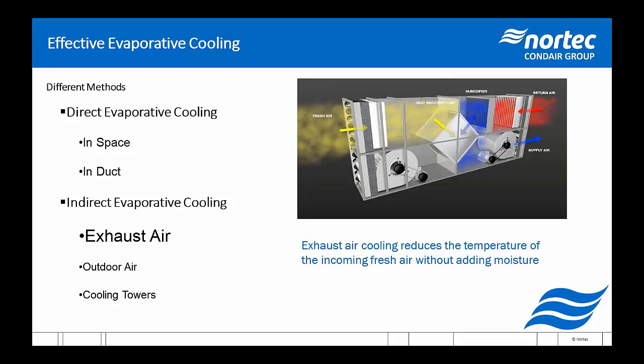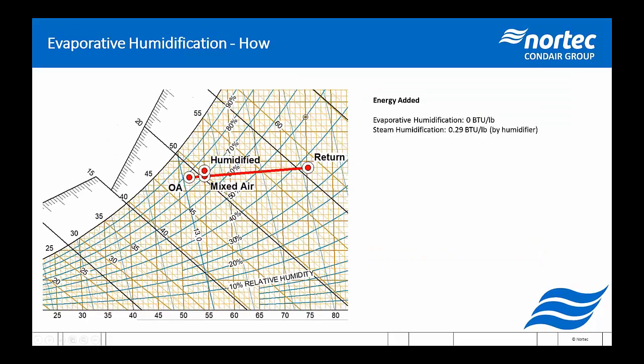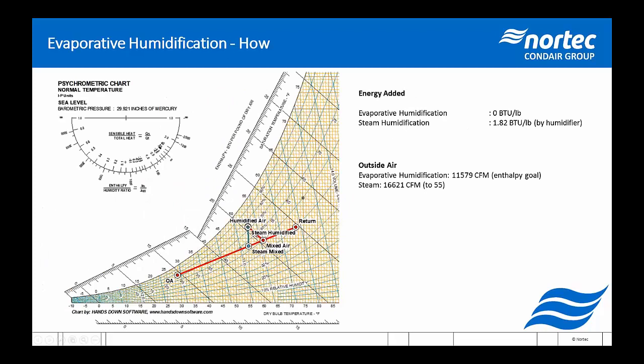Depends on the amount of outside air we need, of course, but typically we'd control it with an enthalpy goal. So if I go back to, well, it's not the best slide. This is the best slide for this. If I go back to this, what we'll be aiming for is we'll put typically enthalpy sensors in the economizer system. So rather than controlling to mix to 55 degrees, we tell the sensor to mix to around 19 BTU per pound enthalpy or something like that. It's easily calculable, and it's typically the same for most buildings. So you end up around 19 or 20 BTU per pound coming in from the outside air and the economizer.